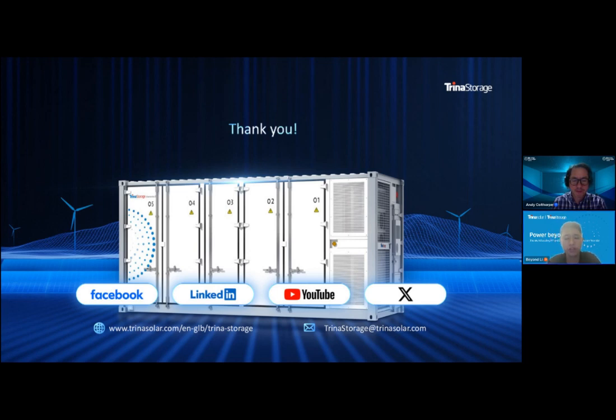As I talked about in the course of the webinar, we have already achieved a high level of compatibility with SMA's PCS. So what exactly are the tests we have conducted behind this system integration? As of now, the first and foremost test is the communication test. There will be communications between SMA's PCS and our BMS.